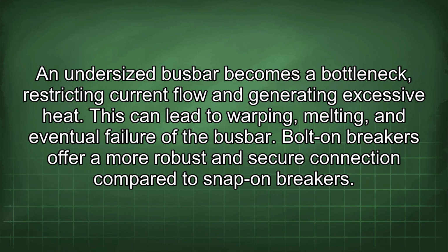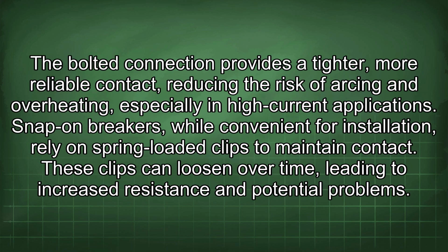Bolt-on breakers offer a more robust and secure connection compared to snap-on breakers. The bolted connection provides a tighter, more reliable contact, reducing the risk of arcing and overheating, especially in high-current applications. Snap-on breakers, while convenient for installation, rely on spring-loaded clips to maintain contact.